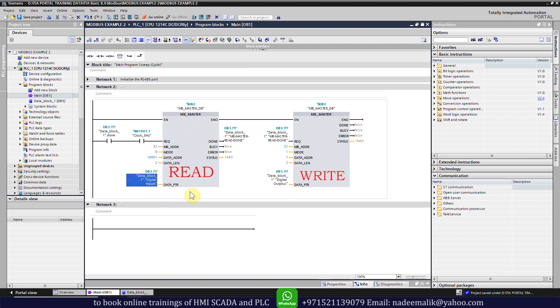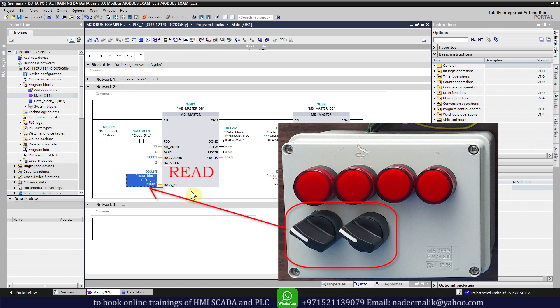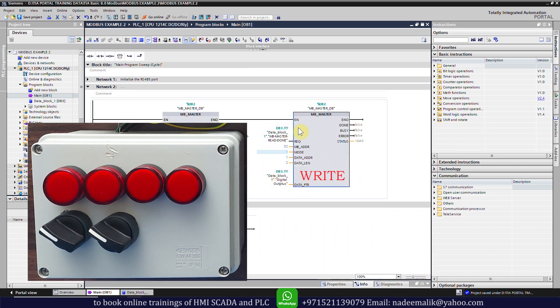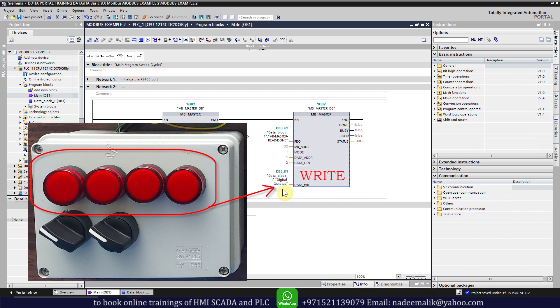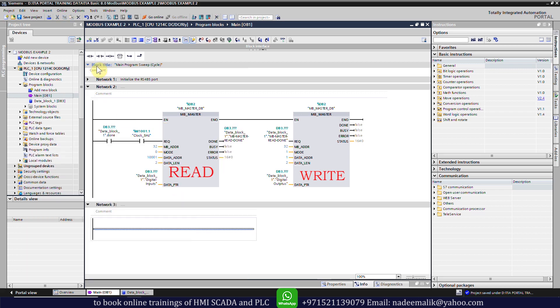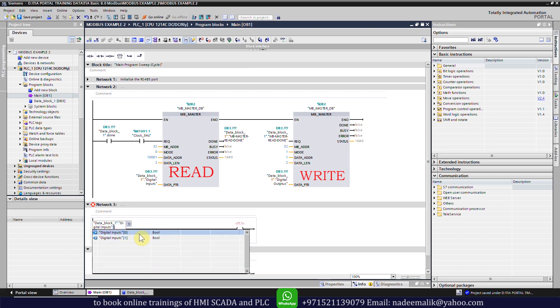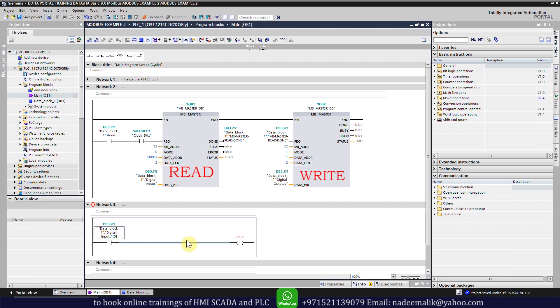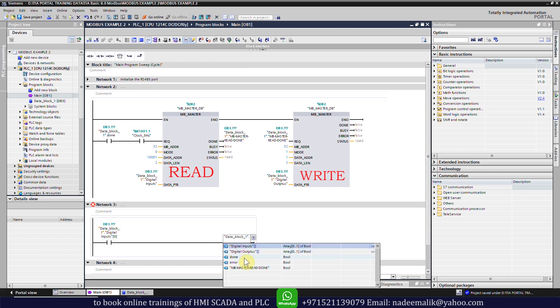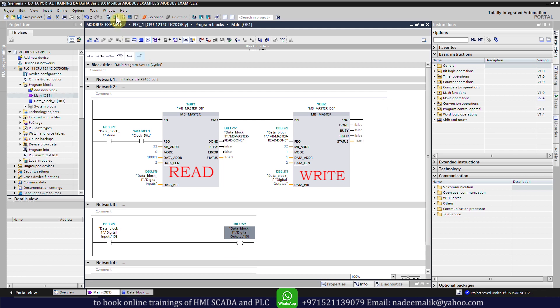Now the MB Master read function will read the status of the digital inputs from the switches connected at the input of the IO module, while the Modbus write function will write the status of the digital outputs — turning the LEDs connected to the relays of the IO module on or off by taking data from the digital output array tags and sending it over Modbus. Next we will insert Network 3, add a normally-open contact assigned to one of the digital input tags from DB3, and an output coil assigned to one of the digital output tags from DB3. With this simple logic, when digital input 0 turns on by activating the selector switch, it will turn on the digital output and the LED. Programming is now complete.